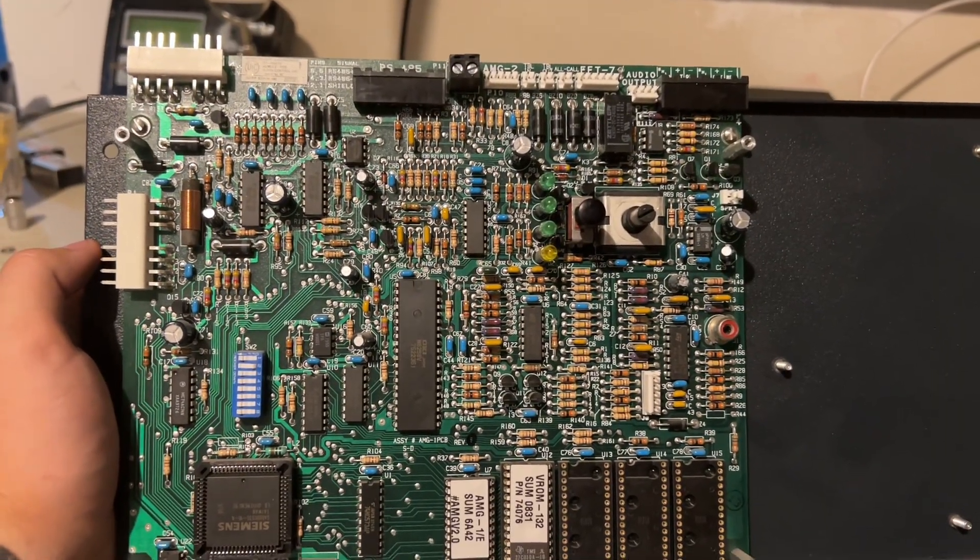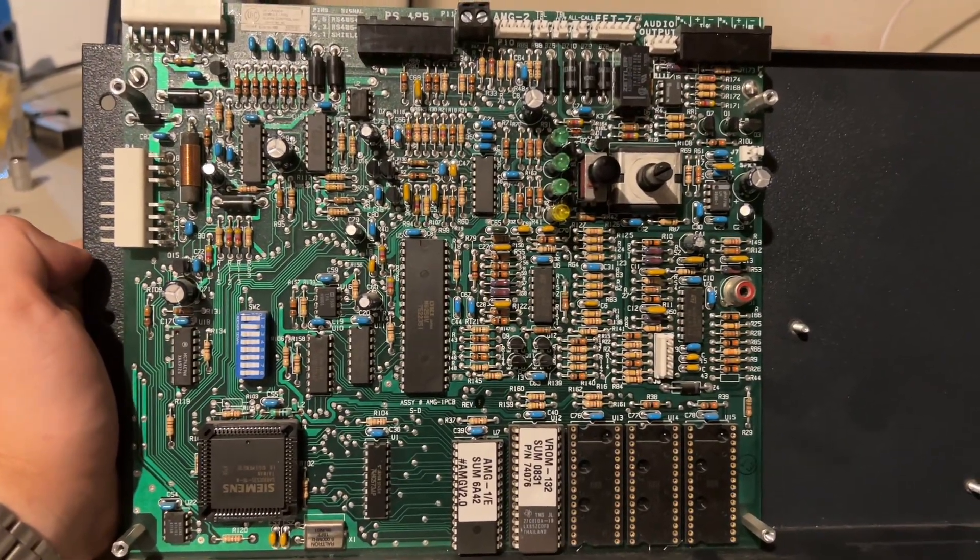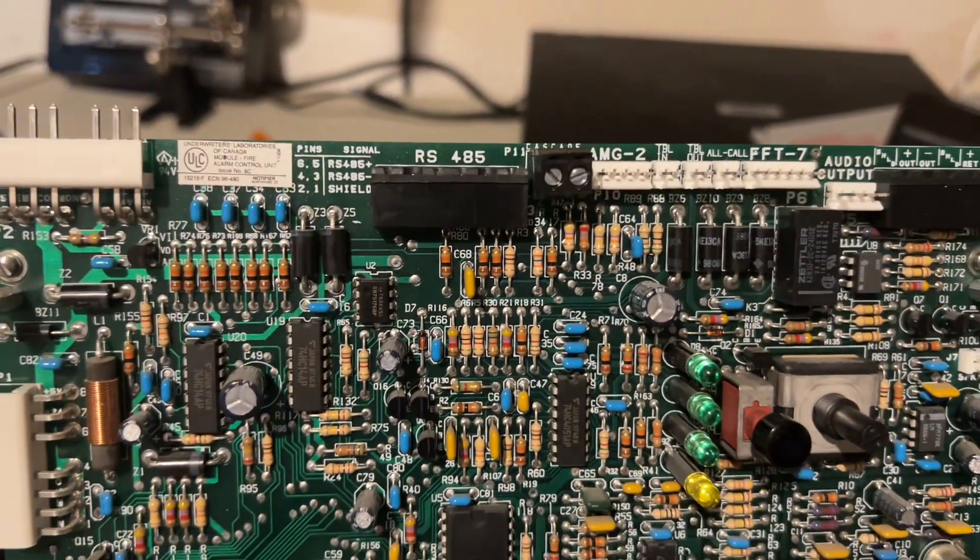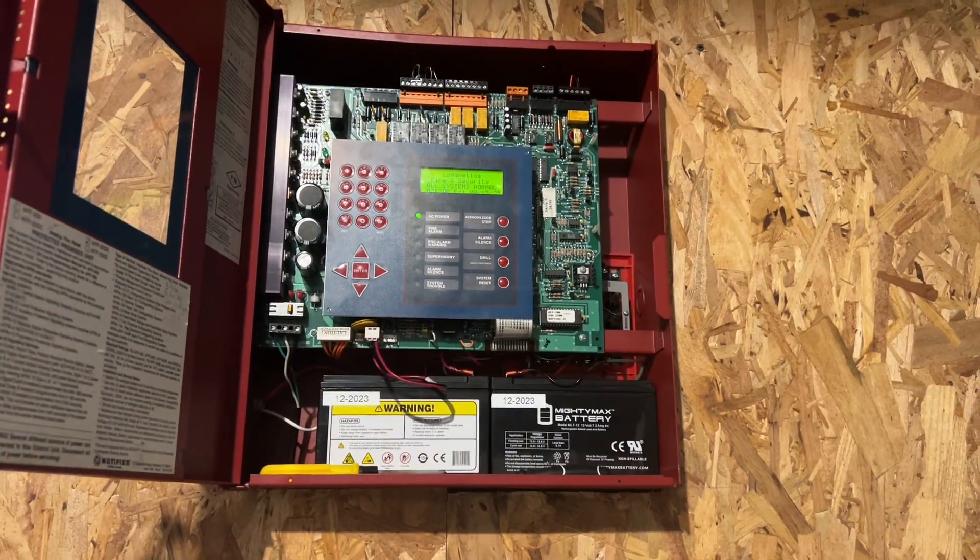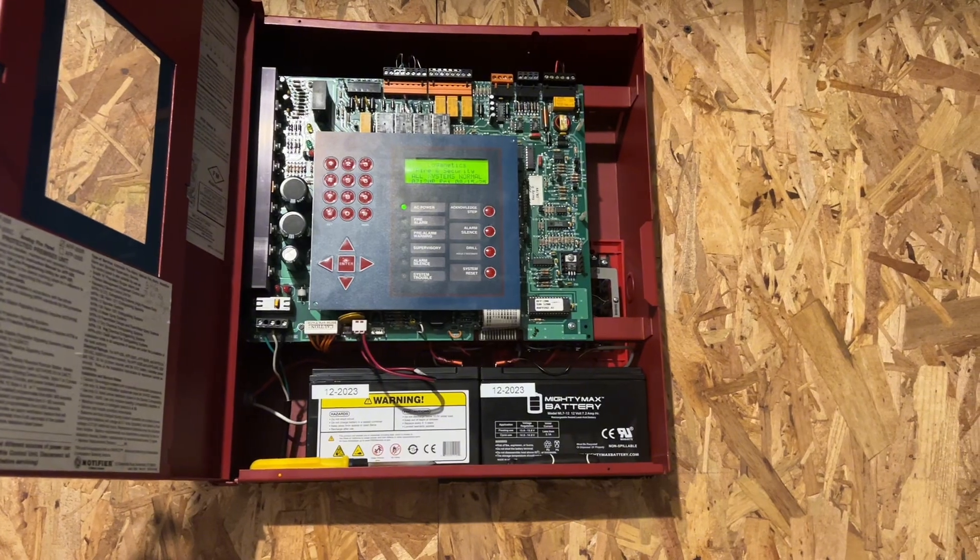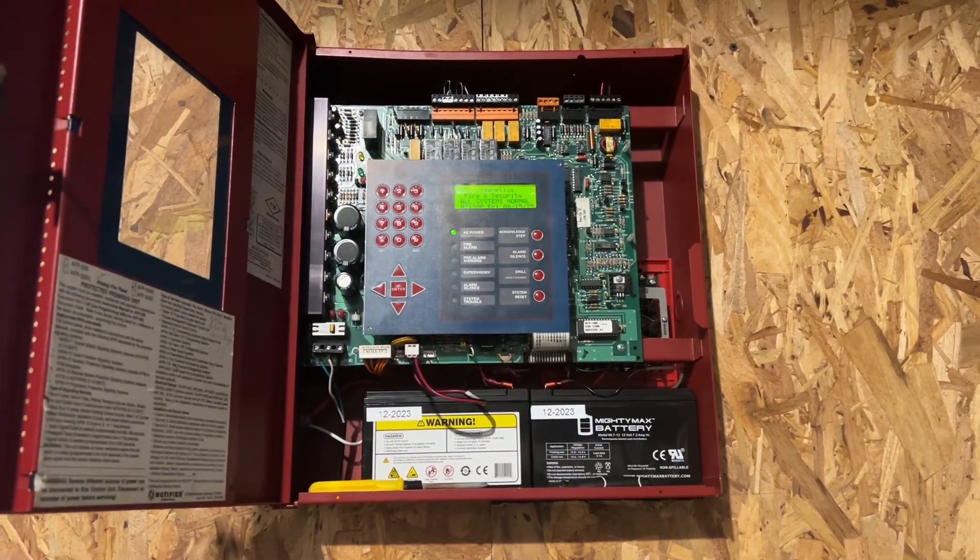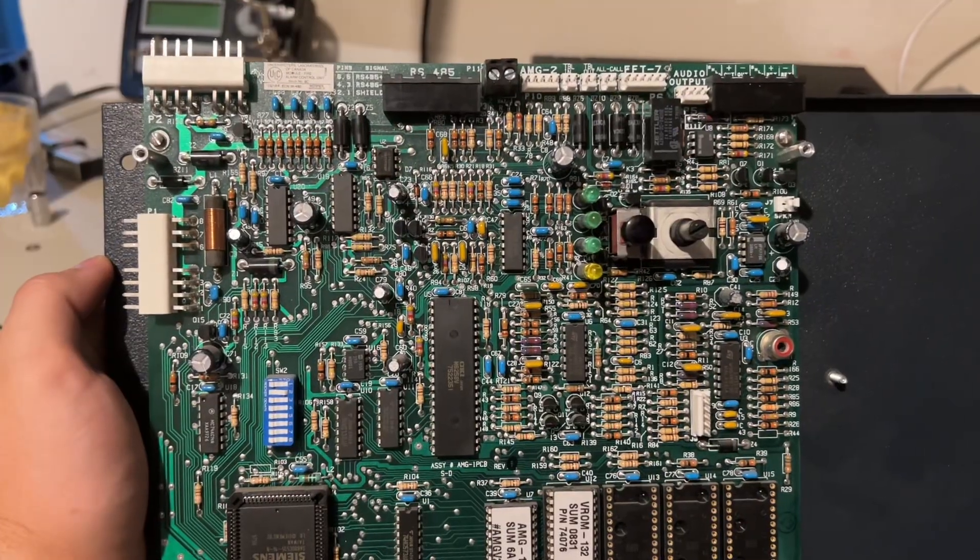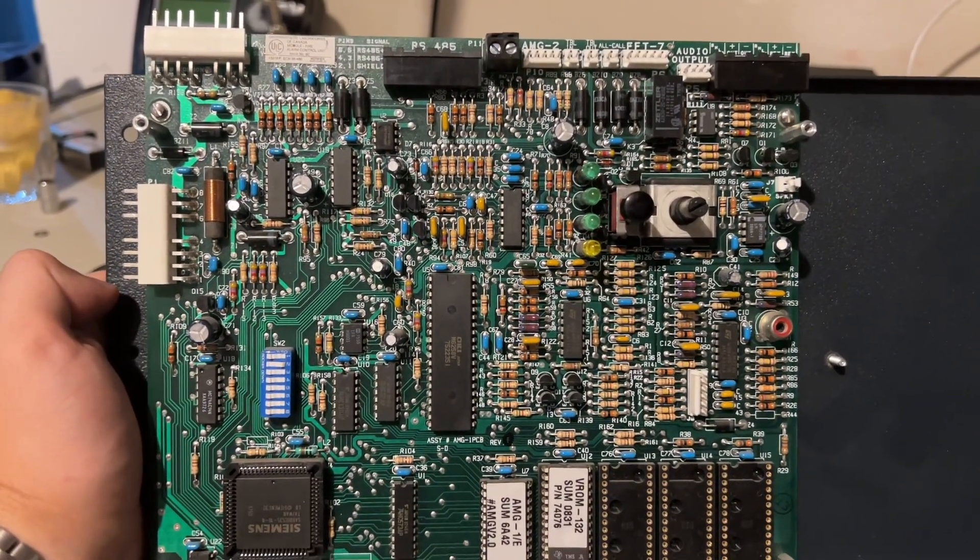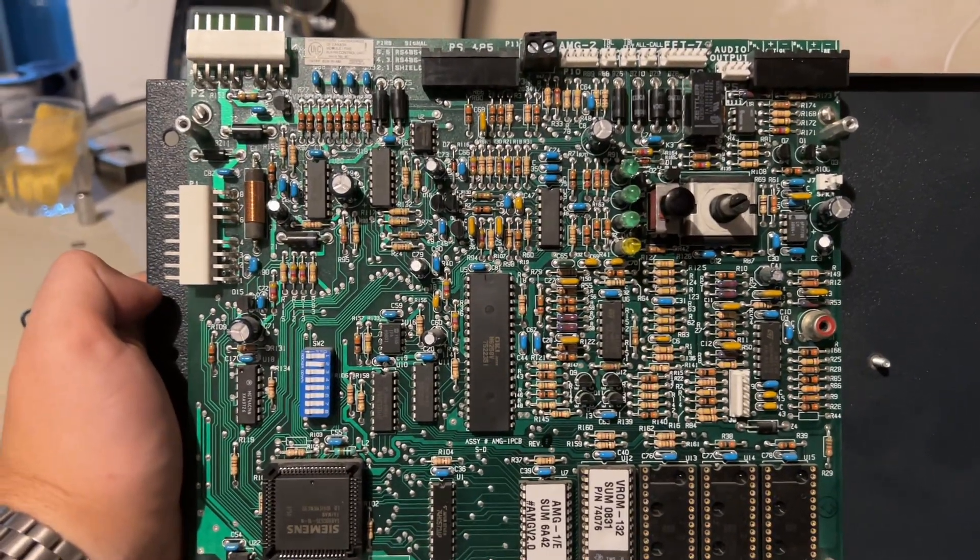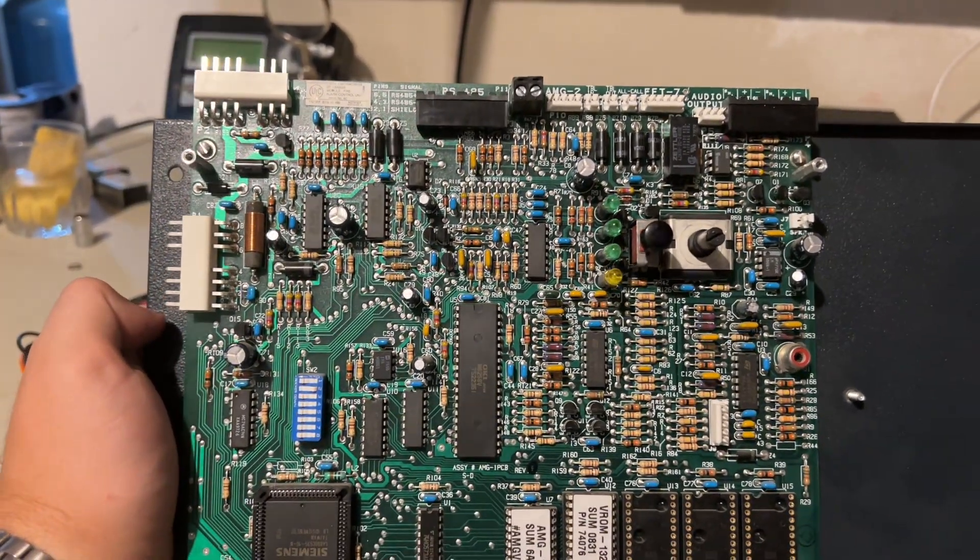Now, you may think that I'm crazy for thinking that this could work on a panel that doesn't support it. Well, the reason why I thought it could work is because it has RS-485. So does that panel. And the AFP-200 uses a lot of the same devices that the AFP-400 can use over RS-485. And also, these AMGs pretend to be annunciators when they communicate. So I'm not entirely crazy for thinking that it could work. But, it did work.